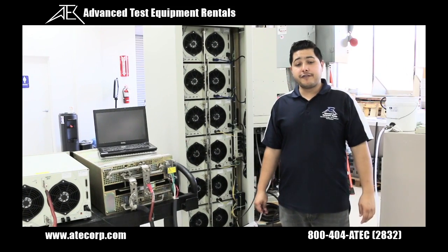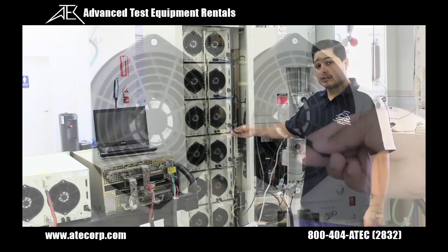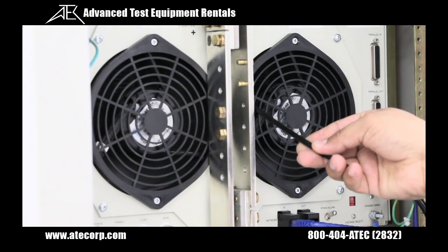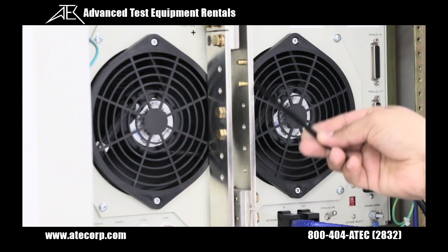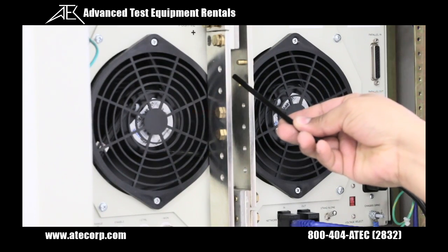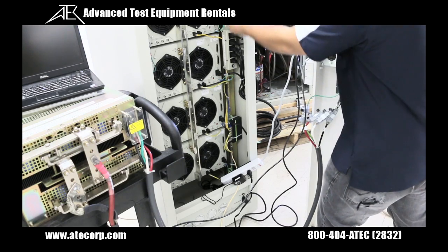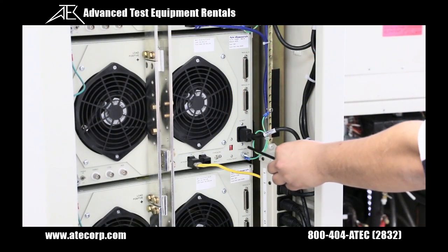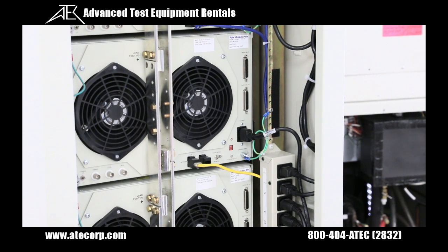We have connected all of the 4760 DC loads in parallel. These bus bars have been installed for parallel operation. You should never let these two bus bars touch, and be aware of screws that may be longer than necessary. Using ethernet cables, we have wired all DC loads to a switch that will be connected to the provided laptop. All units have been set to operate at 115 volts. It is imperative that you connect to a standard 115-volt power source.